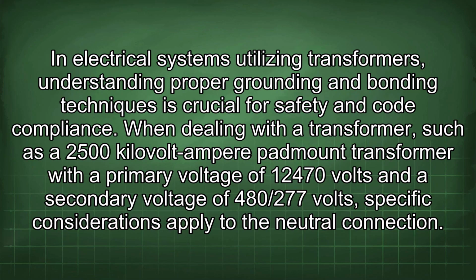In electrical systems utilizing transformers, understanding proper grounding and bonding techniques is crucial for safety and code compliance. When dealing with a transformer such as a 2500 kVA pad mount transformer with a primary voltage of 12,470 volts and a secondary voltage of 480/277 volts, specific considerations apply to the neutral connection.